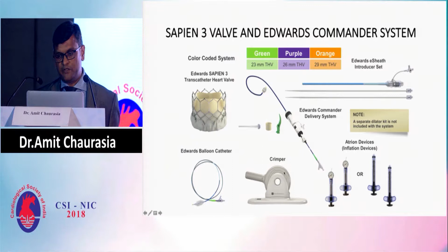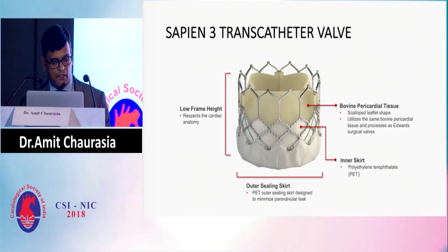The Sapien 3 valve comes packaged with an introducer sheath, the Commander delivery system, the valve, a balloon dilatation catheter, a crimper, and the inflation device. This valve is a bovine pericardium valve which has an inner skirt made of polyethylene terephthalate, and now it has an outer skirt in order to prevent paravalvular leak. The height of the frame is quite low, which has a lot of advantages which I'll be discussing shortly.